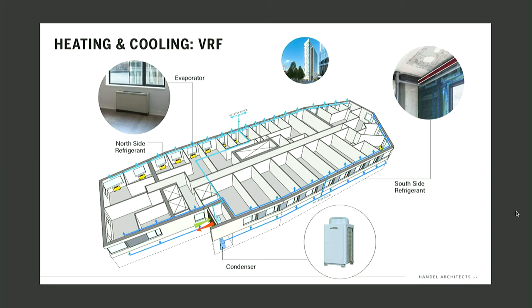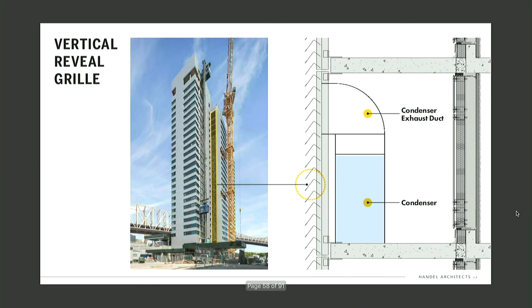We have 2 loops. Cornell's orientation, north and south, was great for this: one loop along the north fed 2 floors, and one loop around the south fed 2 floors. The north side is obviously going to be in heating longer than the south side, so you get that level of control. One challenge with these perimeter loops is getting past columns — we pulled all the columns back from the slab edge about 8 inches, creating a raceway to run the refrigerant. It's a bit tough with hammerhead shear wall conditions and similar issues, but we made it work. So we have these two loops, a south loop and a north loop, and here's that condenser porch.